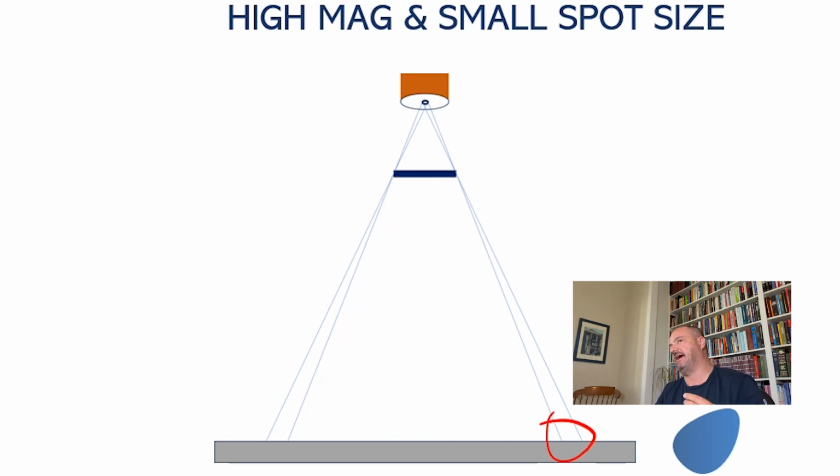So here's to say that magnification plays a huge role in image resolution, meaning that if you lower the mag, you're going to improve resolution by quite a bit, to a point where it doesn't really matter what X-ray source you have, within limits, of course. But as you increase magnification, as you go high mag, the dominant impact on the resolution becomes the spot size.